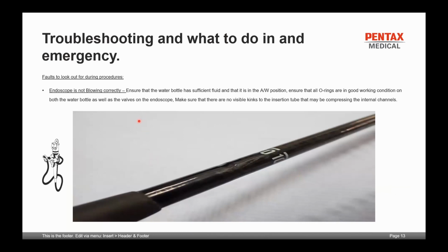Okay, if the endoscope is not blowing correctly, the things you need to look for: please ensure that the water bottle has sufficient fluid in it and that the water bottle is in the air-water position. Some endoscopy companies have a drain facility on their endoscope. So if the drain facility is in a drain position, you will not be getting fluid or water through your endoscope. You will only be purging air through your endoscope. So please have a look at that.